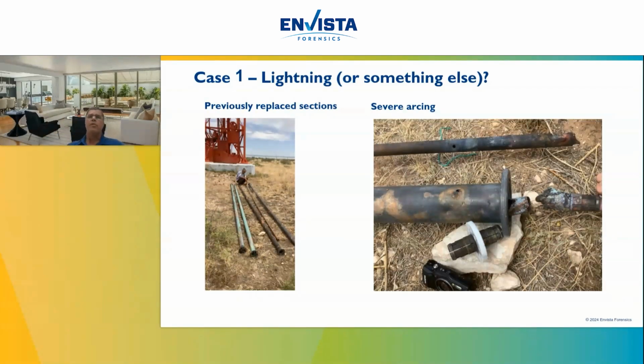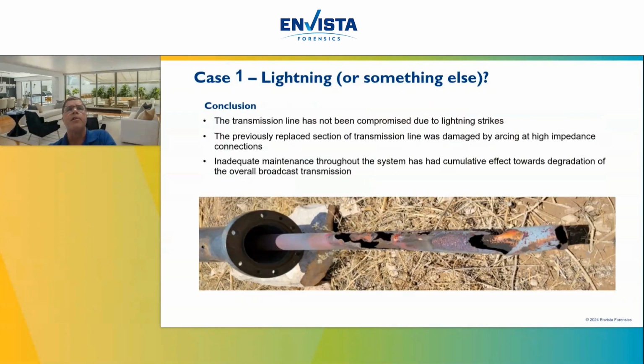And so what we ended up concluding here, because this thermal damage was so well developed through these pieces, and because of some mechanical damage associated with what I believe, or what we concluded, to be arcing because of the high voltage involved here, is that it could have looked like lightning possibly, but these characteristics make it much more likely that this was due to arcing, which was the result of unmaintained or poorly maintained sections of line throughout the preceding decades. So that was our conclusion in this case. Inadequate maintenance throughout the system had a cumulative effect towards degradation of the overall broadcast.